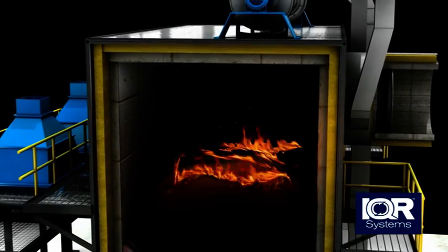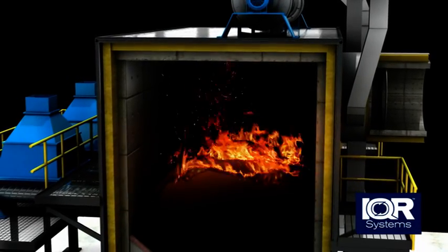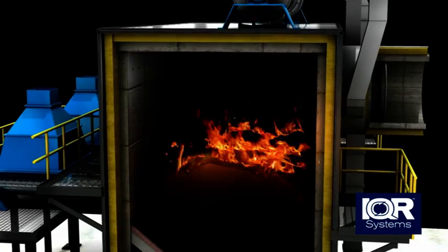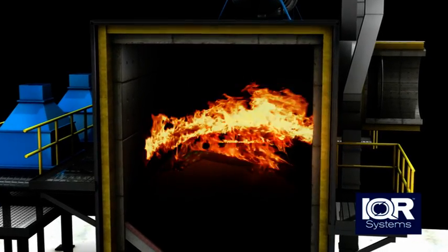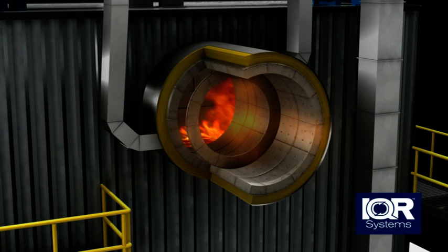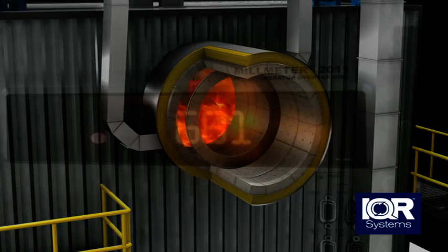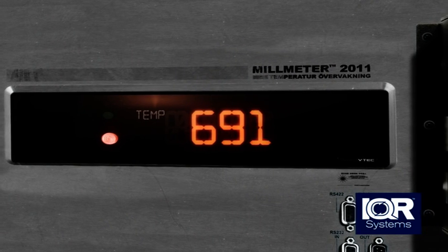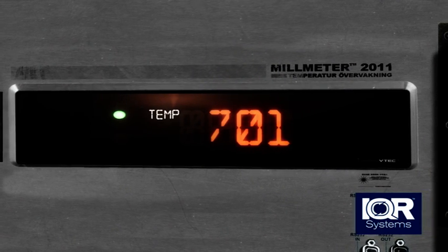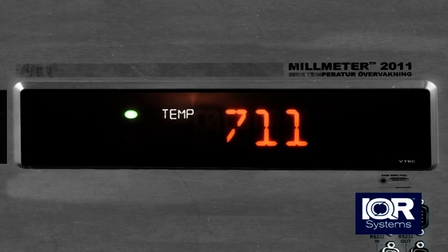The fuel bed burns with an open flame. This is done in order to reach a well tempered gasifier. At a temperature of about 700 degrees celsius, the side doors on the gasifier are closed.